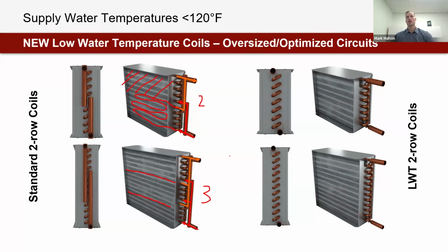What we're doing with the low water temperature coil is we have actually changed it and reduced the circuits to optimize the amount of temperature we can pull out of that coil. So this is a reduced circuit oversized coil. And what that means is if we have 4 GPM in the bottom left coil, we have 4 GPM in the bottom right coil, the one on the right is going to have a much larger delta T because that 4 GPM is transferring energy with air for much longer. It has more tube to travel through. We're going to pull more energy out of it. The delta T is going to be much larger and more optimized at that point.